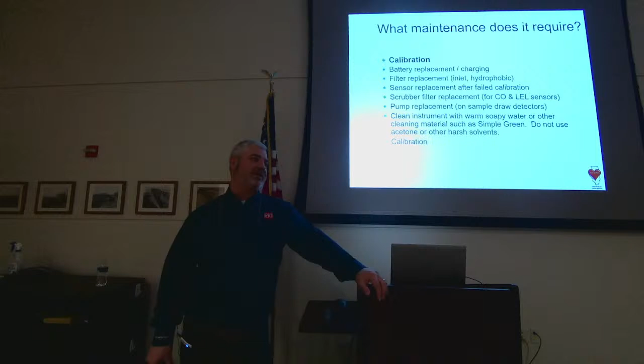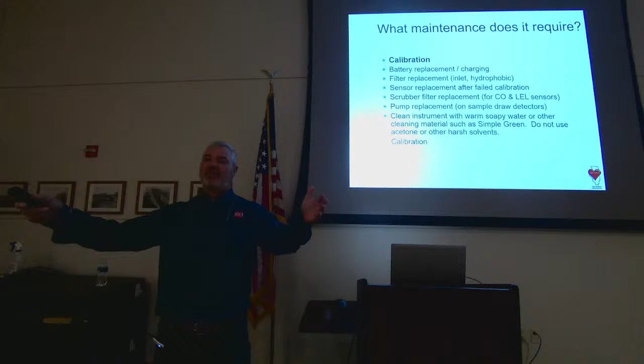These are all conversations you have with the professional that sells you the equipment. Why are you putting it in here? Did you have a problem? Nope. Do you normally have a problem? Nope. Okay, you could probably back off on calibration, but you're going to have a history. You'll know how much degradation is on that fuel cell pursuant to how often you calibrate it and how much correction is needed when they relinearize the sensors.